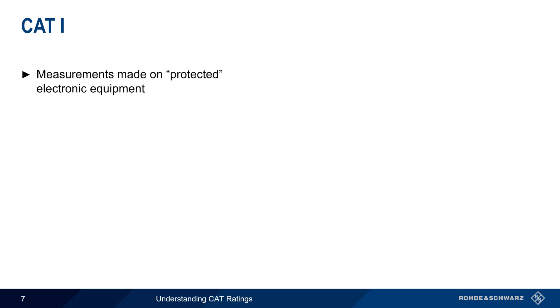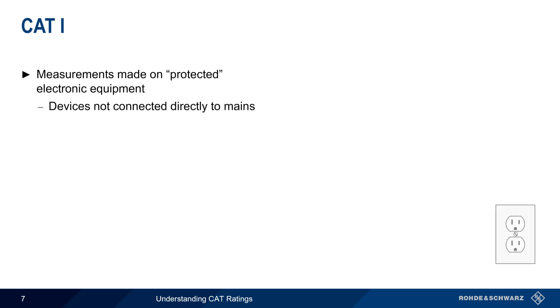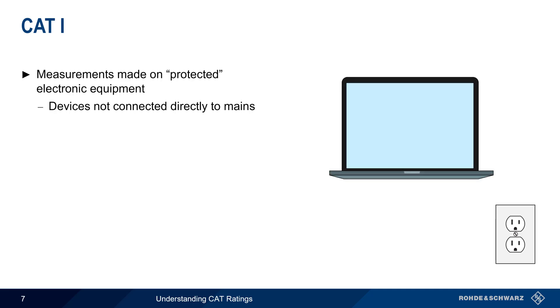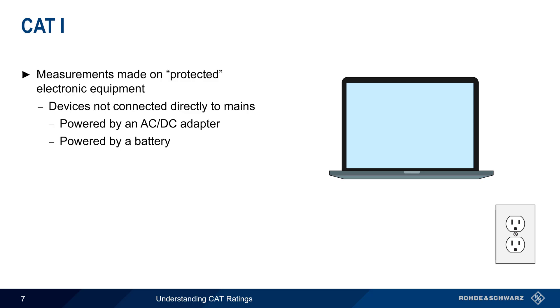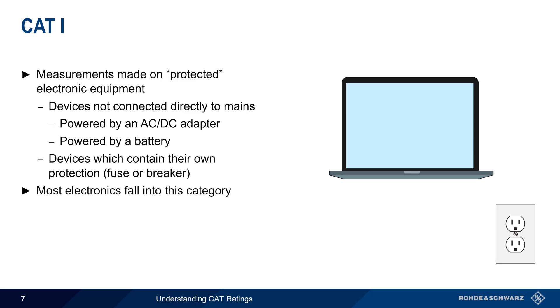CAT 1 applies to measurements on so-called protected electronic equipment. One meaning of protected is that the measured devices are not directly connected to mains. A common example would be a laptop that's powered by an AC to DC adapter or supply, and this would also apply to these same devices when they are running on battery power. Another way in which devices are protected is if they contain their own protection device, such as an internal fuse or breaker. CAT 1 generally applies to most electronic devices, and these devices typically pose a relatively low risk of danger during measurement.